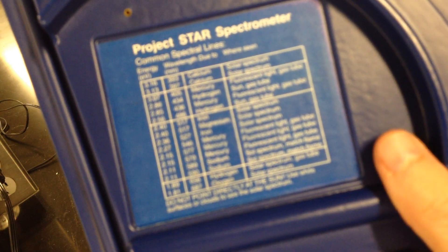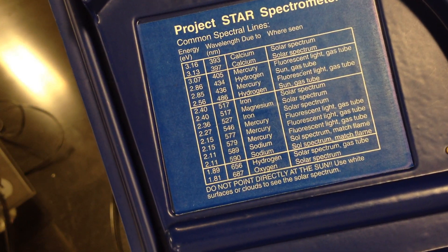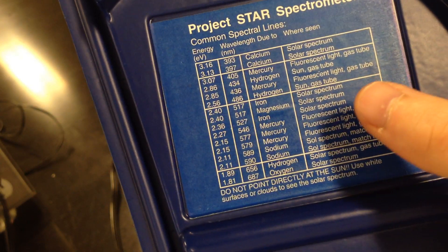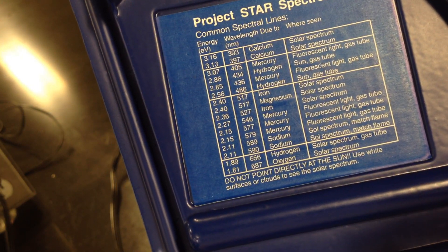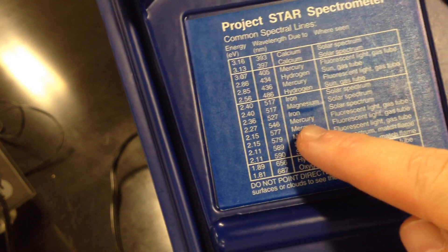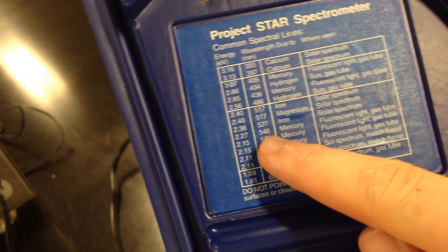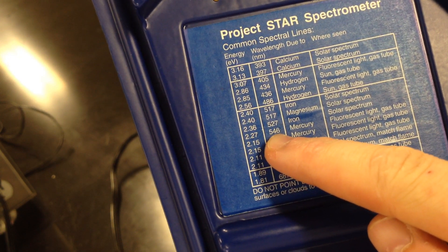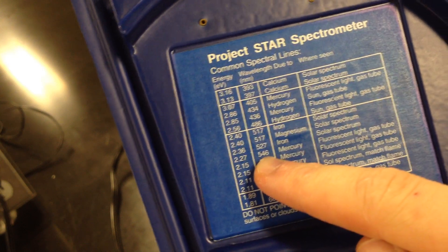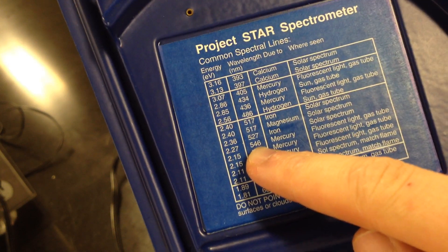If you look on the top of the device, you'll notice that several common wavelengths are listed here. And one way to calibrate this device is to use the fluorescent lights that are in your laboratory. You'll notice that mercury is on this list, and it's got a line at 546, which is its characteristic green line.